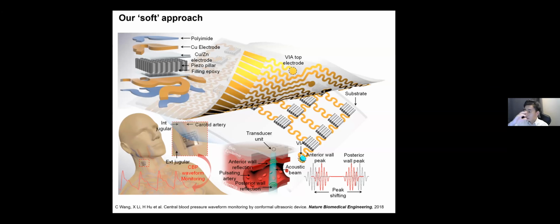When the ultrasound propagates between two different media with two different acoustic properties, it will get a reflection at the interface, and this reflection will bounce back and be received by the transducer. So the propagation time from the transducer to the first interface and then bounce back, this total reflection time is called time of flight.